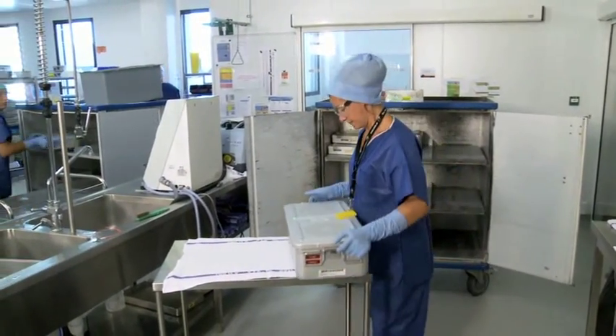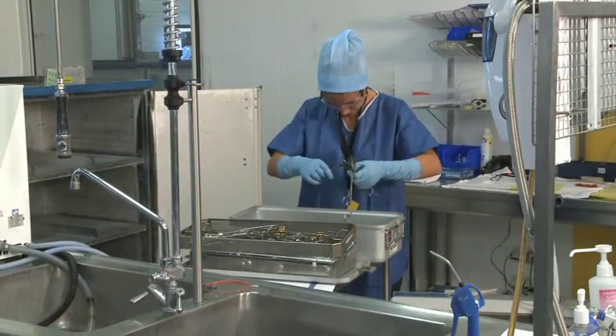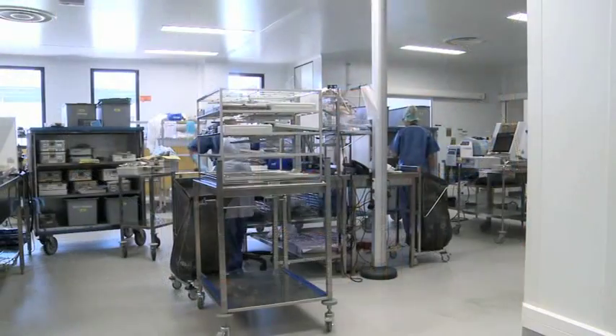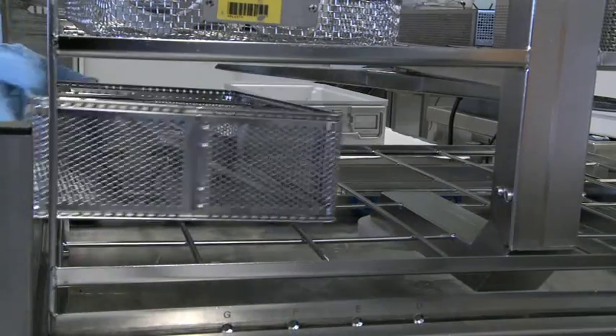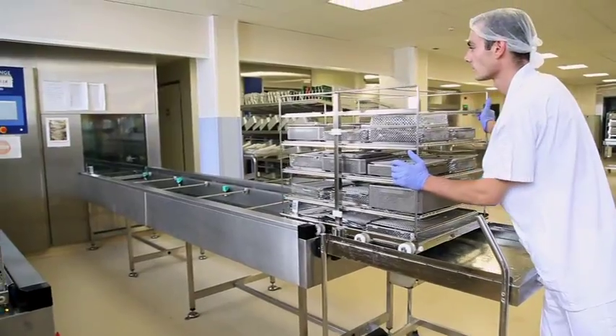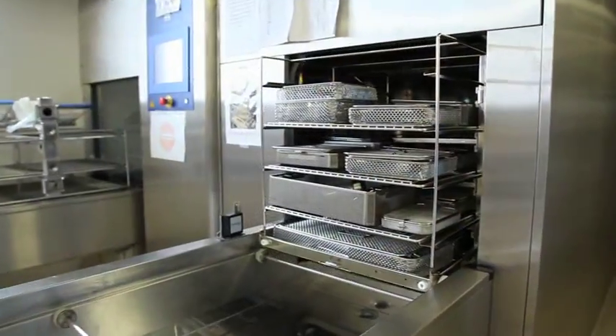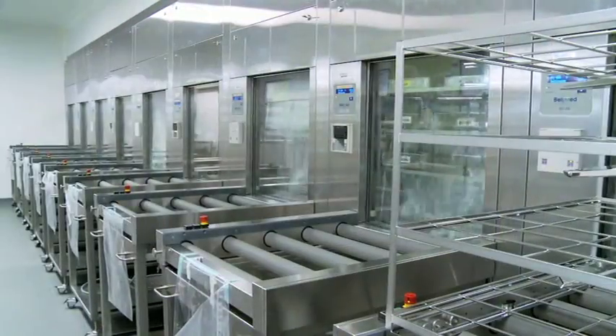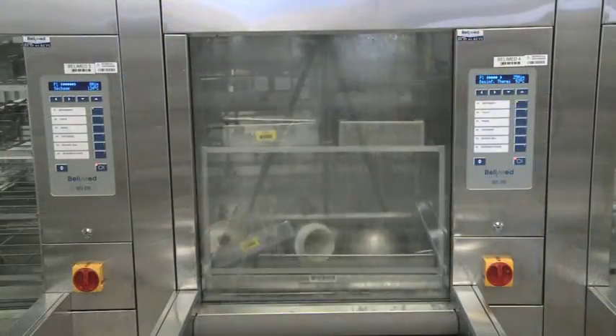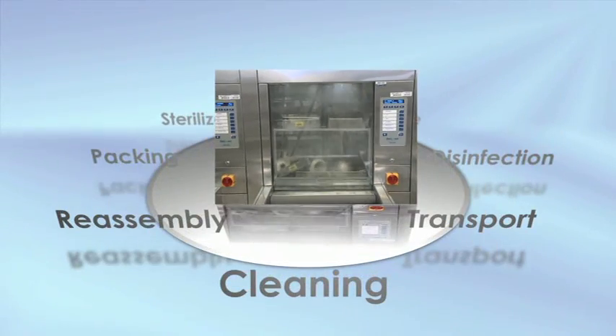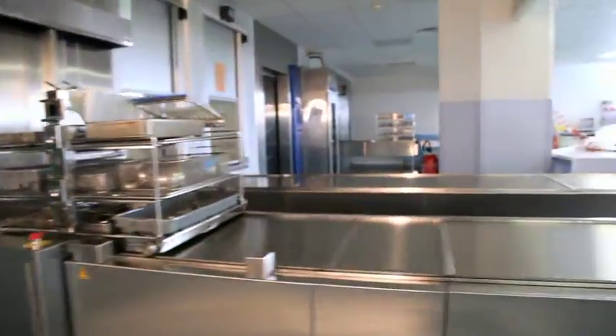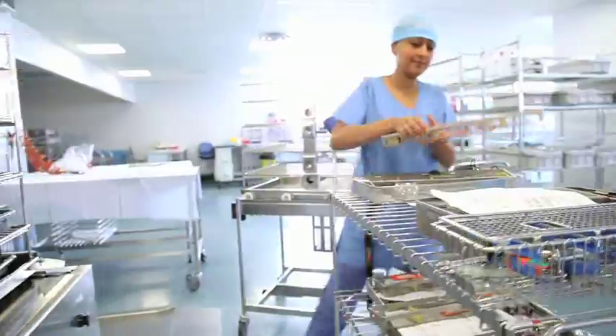The MDs are taken to the cleaning zone in their carriers and are sorted by patient, placed on open trolleys and put into the washing machines for a cycle of about 1 hour washing, disinfection at nearly 90 degrees and drying at about 100 degrees. When they leave the washing machines, the MDs are taken to the reassembly zone.